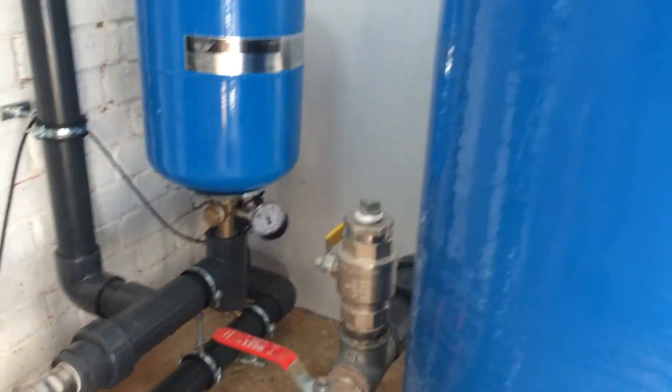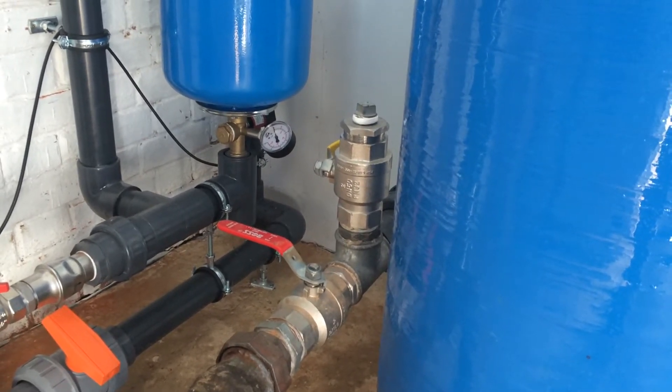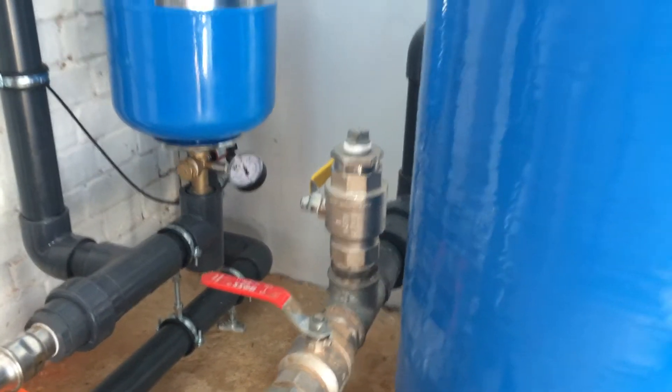We've put a backwash valve in as well. We're finding a lot of iron still in the distribution system which needs to be back-flushed out, so we put one of those in for the client as well.